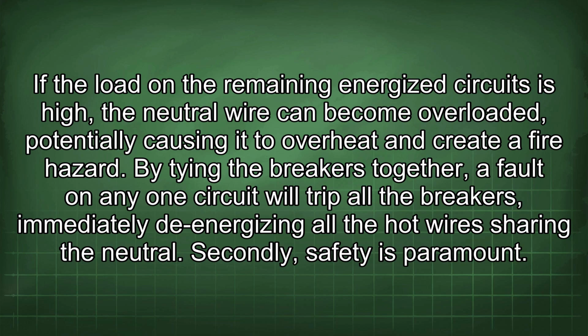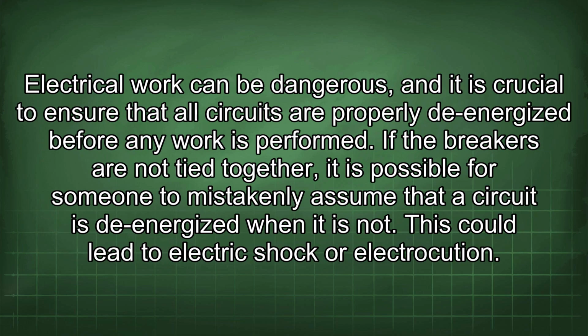By tying the breakers together, a fault on any one circuit will trip all the breakers, immediately de-energizing all the hot wires sharing the neutral. Secondly, safety is paramount. Electrical work can be dangerous, and it is crucial to ensure that all circuits are properly de-energized before any work is performed.